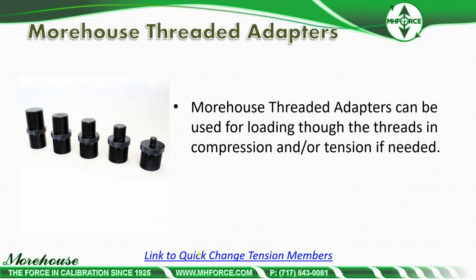Morehouse threaded adapters, these adapters that you saw for tension, can also be used for compression, for loading against the bottom base. We can also put a ball adapter. They can also thread into the load cell and load them against the shoulder, and we can put ball adapters on them. Pretty cool. Again, the best case scenario is just good, better, best. Best is always to have it however the customer's using it. So on the better side, if you don't have that, these would be on the better side of adapters, just to facilitate the calibration and provide a good result and match.